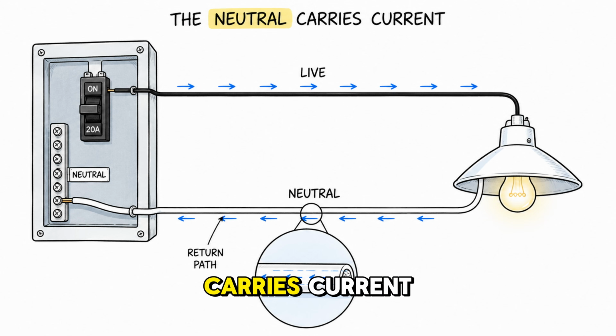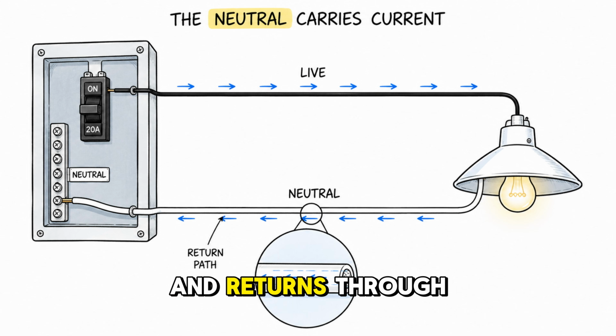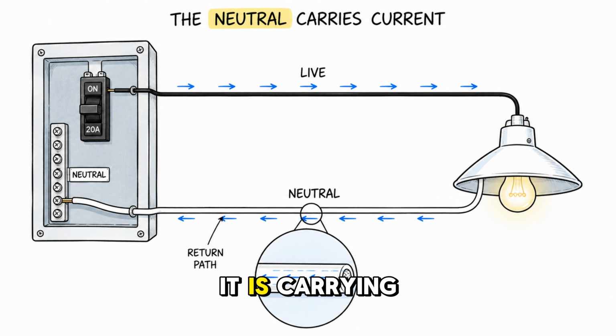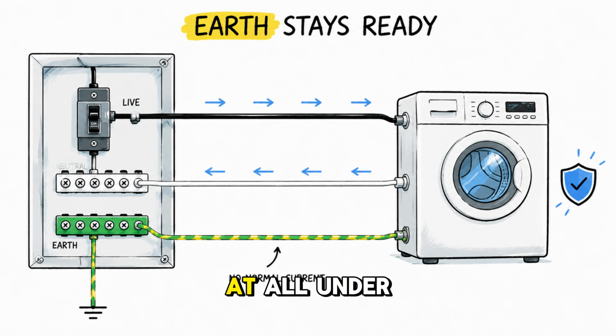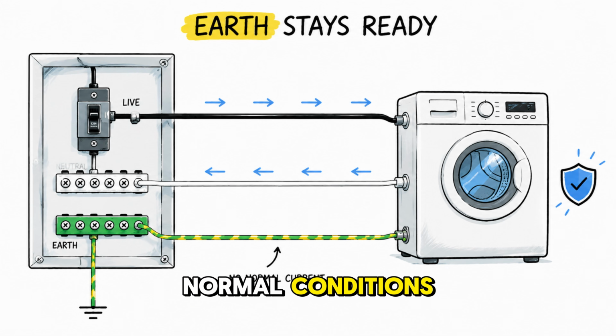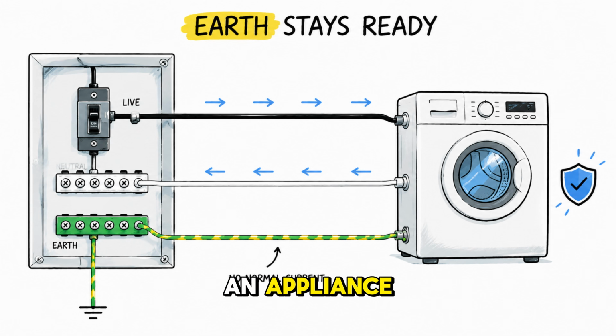The neutral wire carries current continuously during normal operation. Every time an appliance is turned on, current flows through the live wire into the device and returns through the neutral wire. The neutral wire is active. It is carrying load current right now. The earth wire carries no current at all under normal conditions. Its entire purpose is to provide an emergency escape path for fault current if something goes wrong inside an appliance.